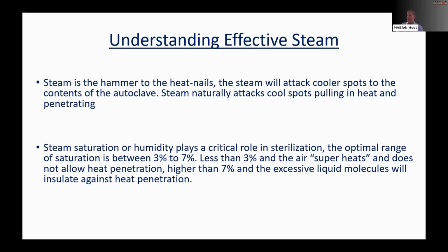In life sciences, they don't run Bowie-Dick tests because they're generally running other things, so you don't know if you're actually getting proper penetration. I've found that most people don't understand the penetration of the steam, and that's where it's critical. Without it, if you just use regular dry heat, you end up having to bake it from the outside in, whereas steam actually drives in and pulls into wherever you're trying to penetrate.